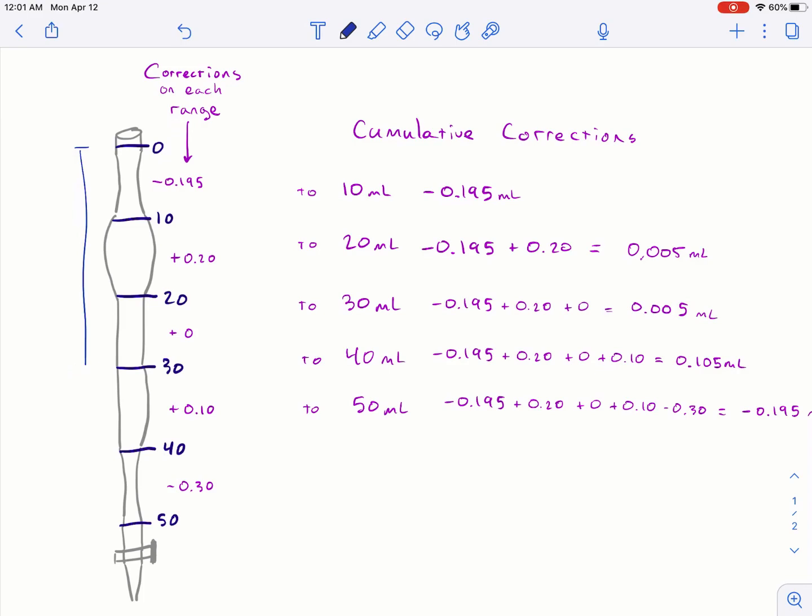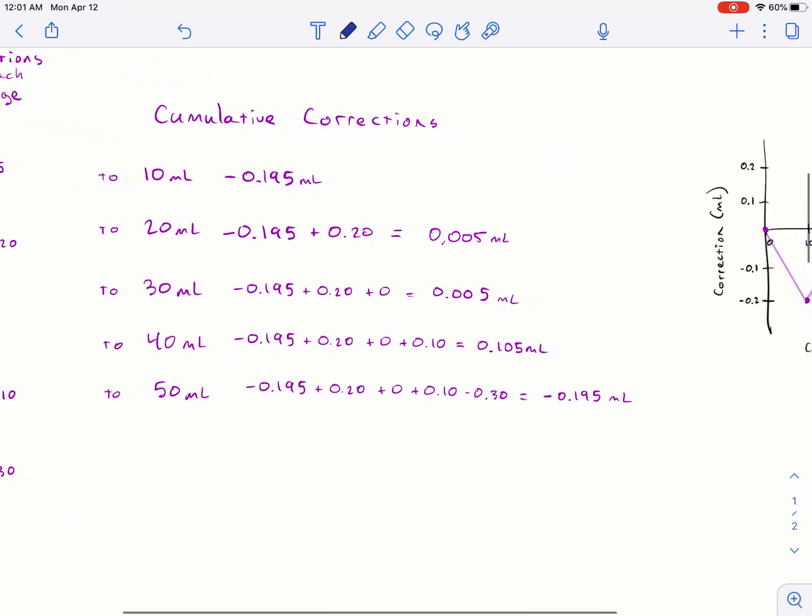Or if you did it like kind of like I did it and conceived of it in my head, you take these numbers for each range. This is 30 to 40. Here's the correction for it. And then you basically just add all your corrections up as you go down the burette. And then you calculate kind of a cumulative number. So here's me adding them all together. This is just addition. That's all that is. So I add them all together and I get these cumulative corrections.